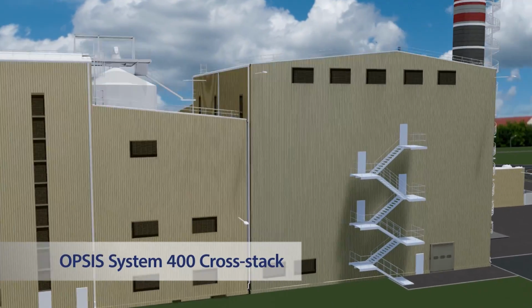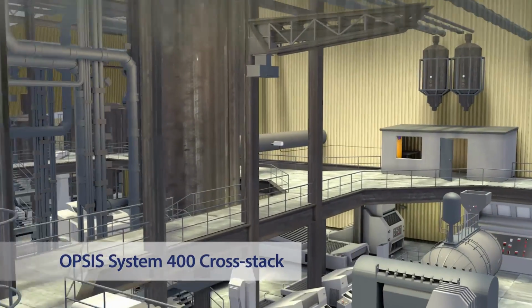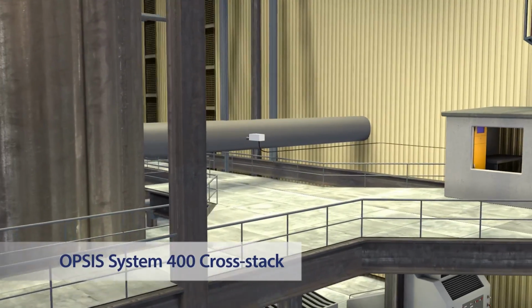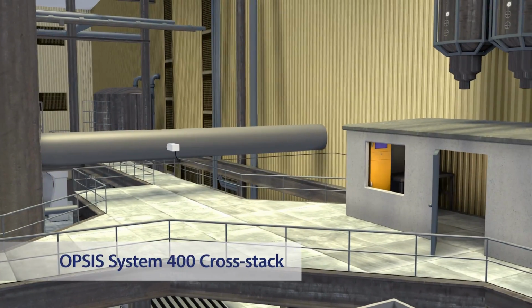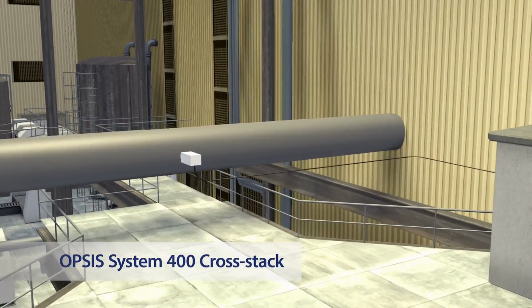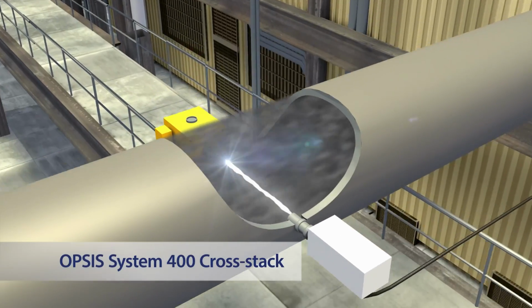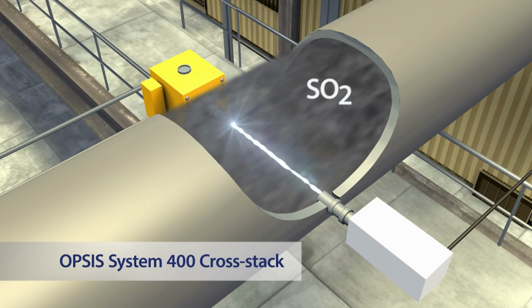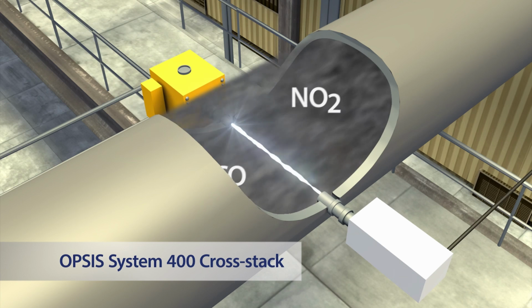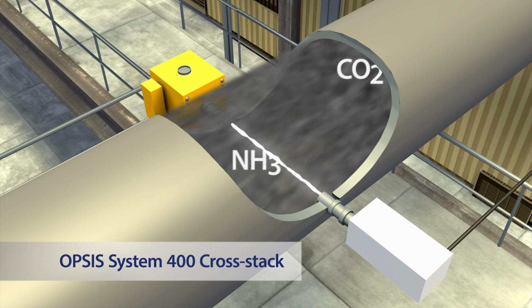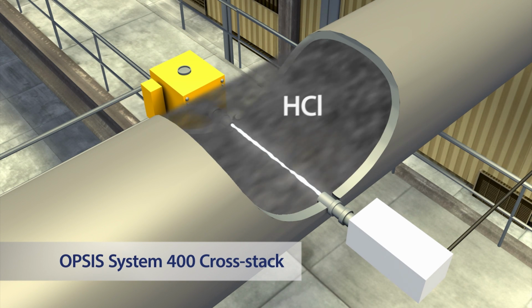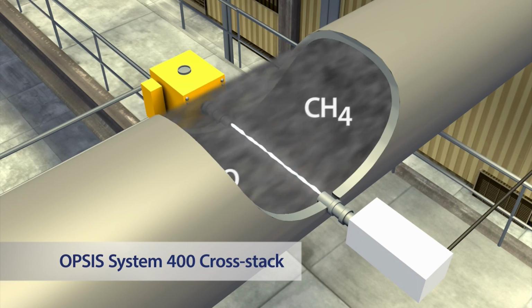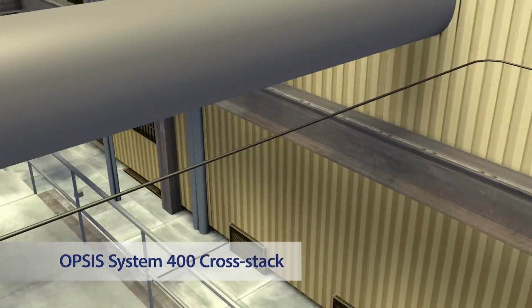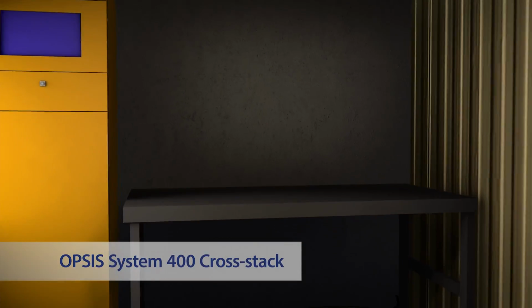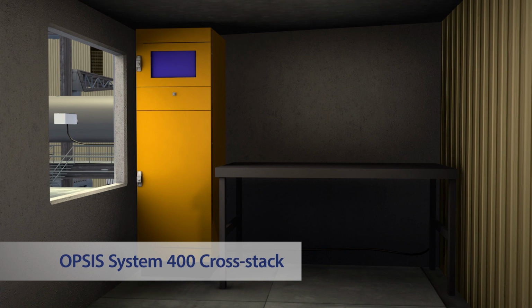This installation is carried out with the emitter and receiver positioned on either side of the duct or stack. The cross-stack method measures the flue gas components across the duct with a beam of light. Using the OPSIS DOAS technique, this system is a non-contact method with fast response and low maintenance. The light is led from the receiver to the analyzer via fiber optic cable. The analyzer can be placed in a separate room.